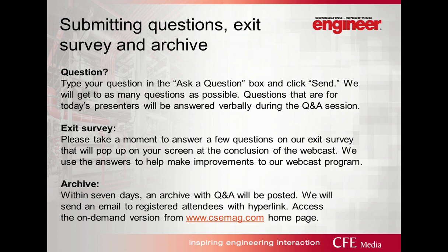Sure. In assisted living, we mentioned that anything that's ventilator-based is listed within NFPA 99 and FGI guidelines. And again, that always comes back to the risk assessment. That's the main takeaway that I'd like a lot of the participants to have: when you're wondering, do I need emergency power and what branch does it fall on, you're going to ask yourself which category this space falls in. Which level does it fall under? Is it level 1 or level 2? Can anybody die? Can they be injured? Are they just going to be inconvenienced?